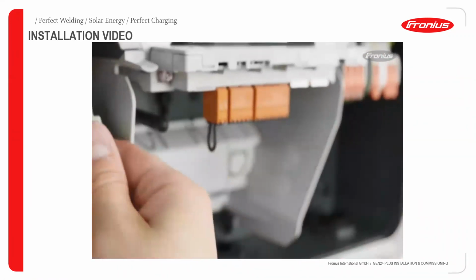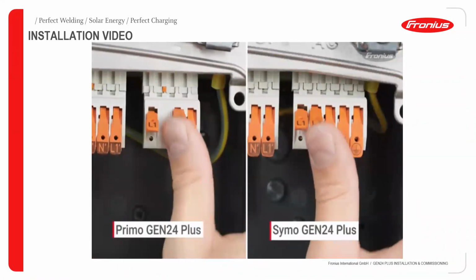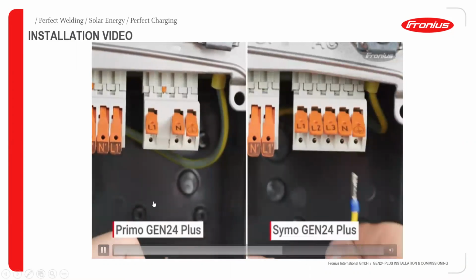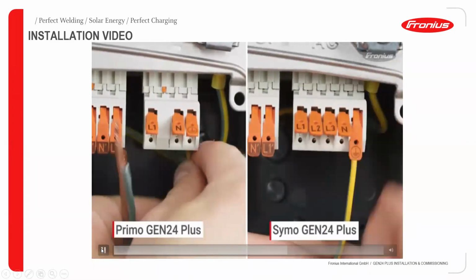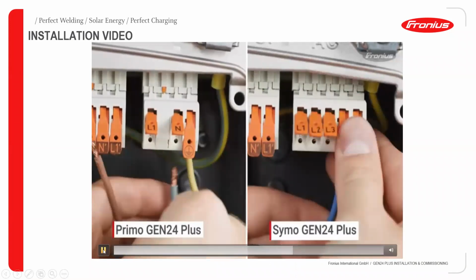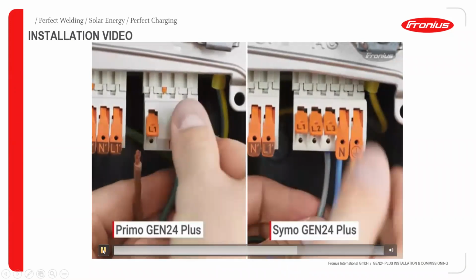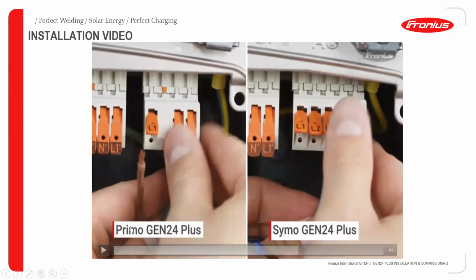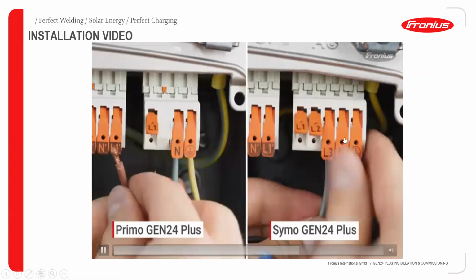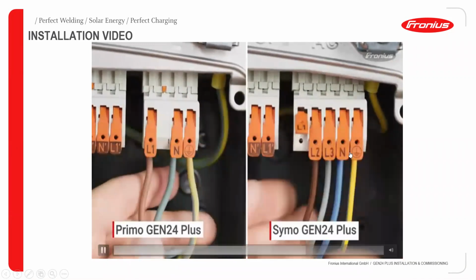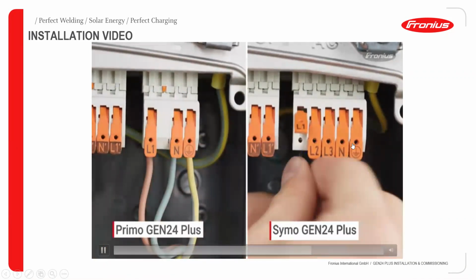Once the DC side has been connected, you can go ahead to the AC side to continue the installation. For the primo, which is single phase, it's going to be 3 terminals: L1, neutral, and ground. For the 3-phase, it's going to be 5 terminals, that is the 3 phases, neutral, and of course ground, as you can see.